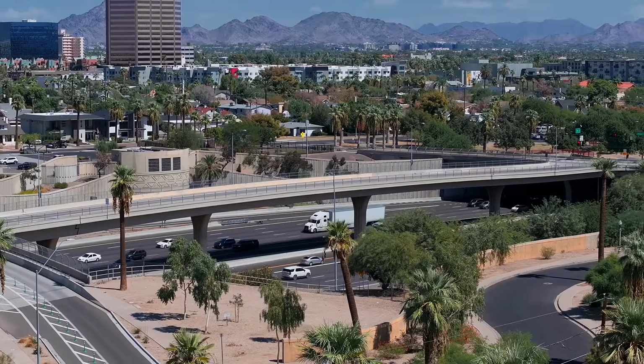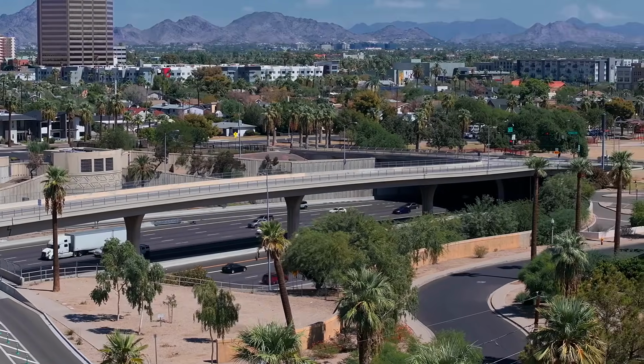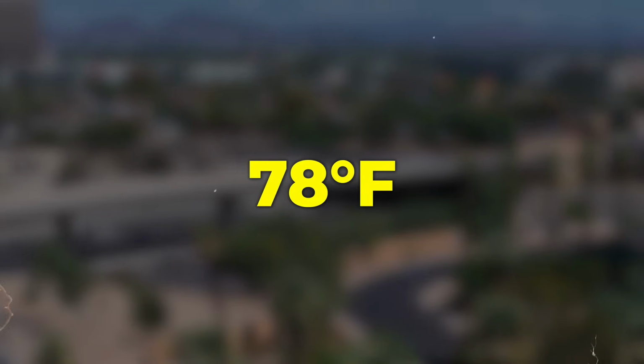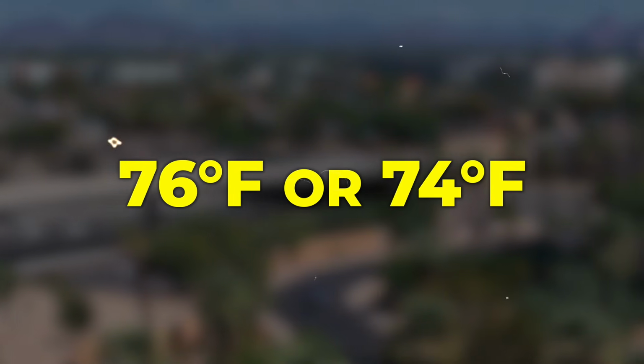For example, in Phoenix, Arizona, design conditions are typically around 78 degrees. Now, most people are able to hit 76 or 74 with their systems, even though my in-laws look at me like I'm crazy when I set the temperature at 74 degrees when I visit Phoenix. But the bottom line, if you have a system that is icing on a continuous, chronic basis, the next culprit I look at is ductwork and system design conditions.